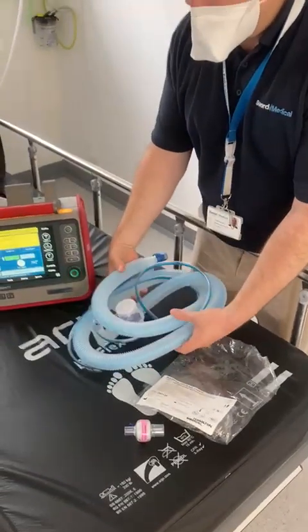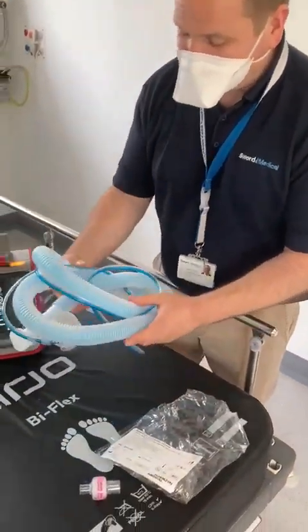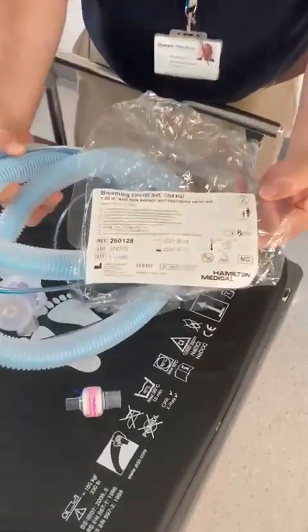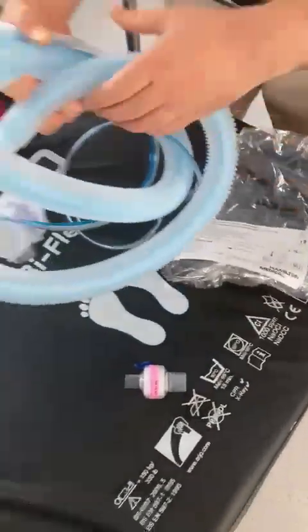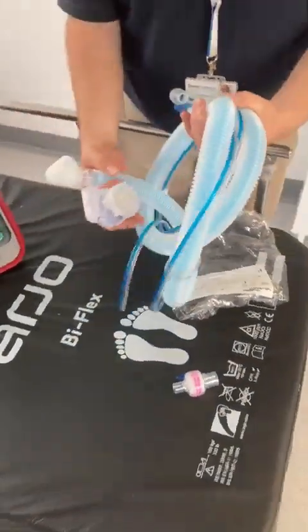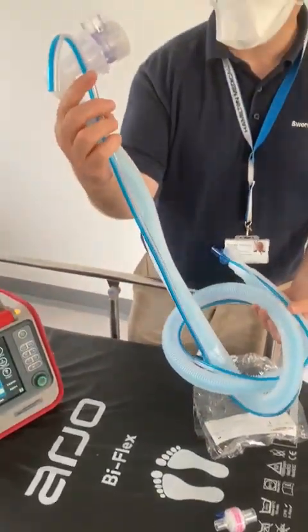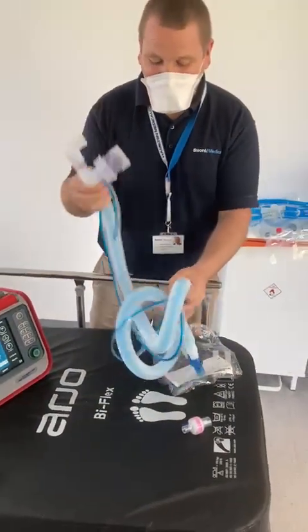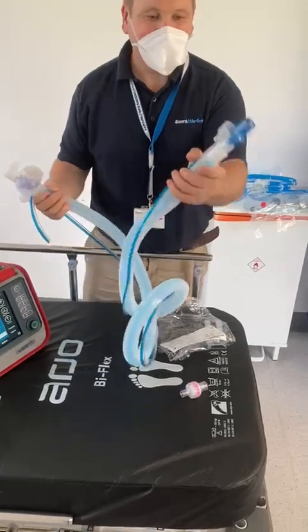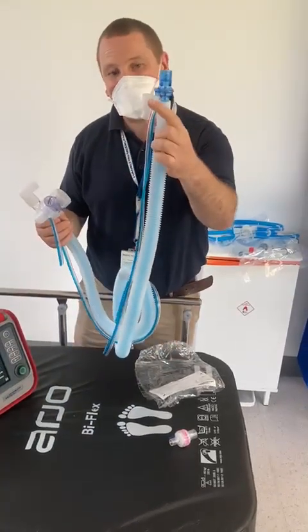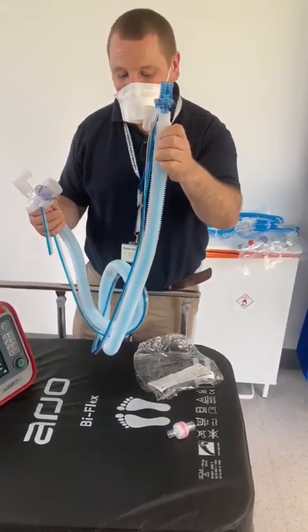So now I'm going to put on an adult pediatric circuit, and this is the adult pediatric circuit. It comes in with the label here, and this is what comes in the adult pediatric circuit. We've got our expiratory valve here, and the flow sensor tubing on the ventilator end, and then on the patient end I have my flow sensor with my little connector which comes with every circuit. That's going to allow me to calibrate the flow sensor.